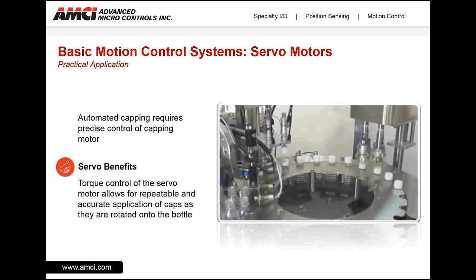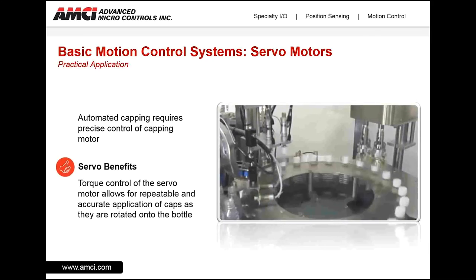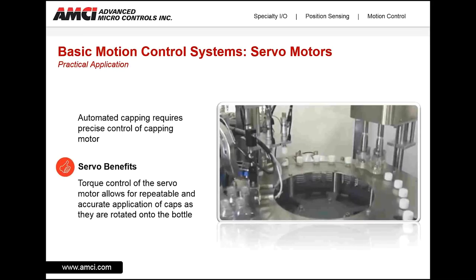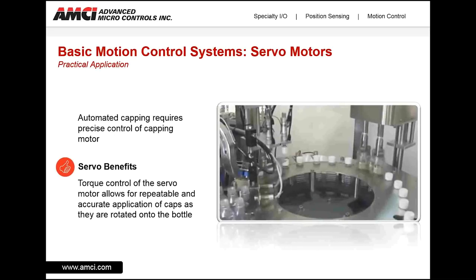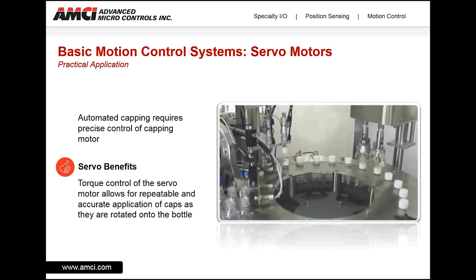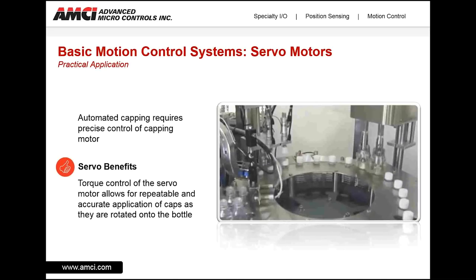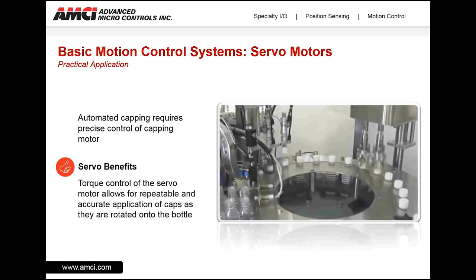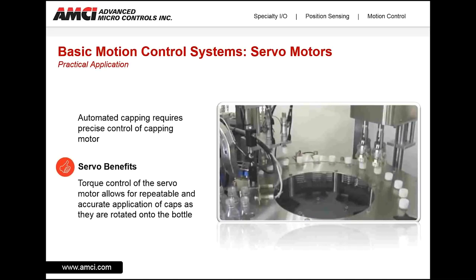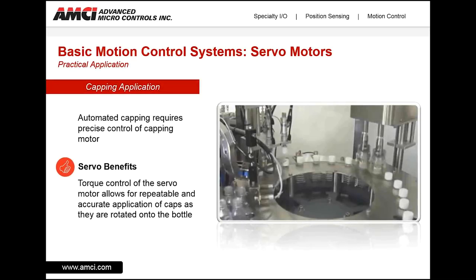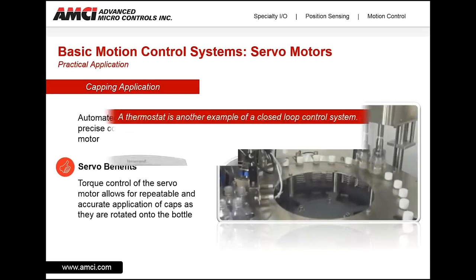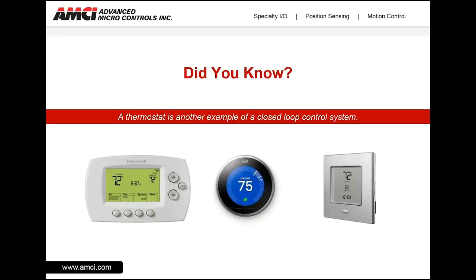A good example of how servos take advantage of their closed loop design is a capping application. One of the advanced features a closed loop system can provide is torque control of the motor. Through continuous monitoring of motor feedback, the control unit can limit the current to the motor, thus limiting the torque. This allows for repeatable and accurate application of the caps as they are rotated onto the bottle. A thermostat is another example of a closed loop control system.